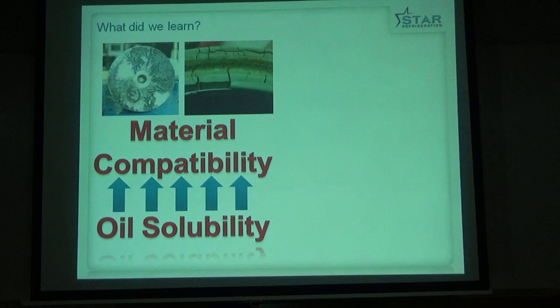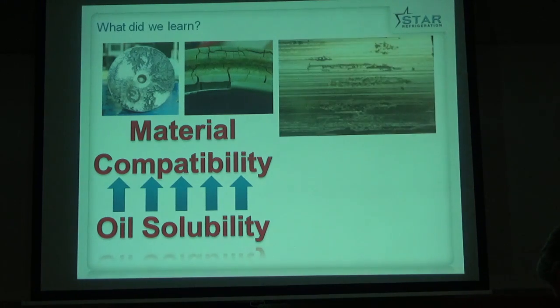This is the resin seal on the bottom of an oil filter, which with the high pressure and temperature has failed to stand up to the operating conditions, so we've had to look at alternate materials for them. And this is a metal to metal surface from within the compressor, where again this oil solubility and cavitation has caused problems on the steel as well as on the aluminium.